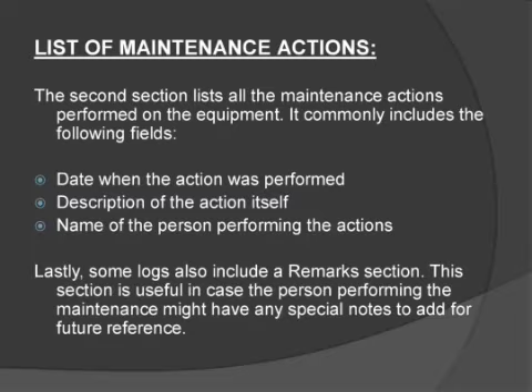The second section lists all the maintenance actions performed on the equipment. It commonly includes the following fields: the date when the action was performed, a description of the action itself, the name of the person performing the action, and lastly, some logs also include a remarks section. This section is useful in case the person performing the maintenance has any special notes to add for future reference. Here, the logbook will have the name of equipment, serial number, purchase date, location, manufacturer or model, person responsible for the equipment, date in service, description of the maintenance, maintenance performed by whom, and additional notes. We have to maintain all this information in the logbook.